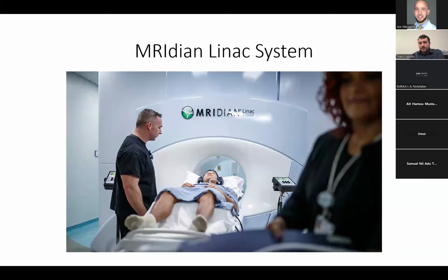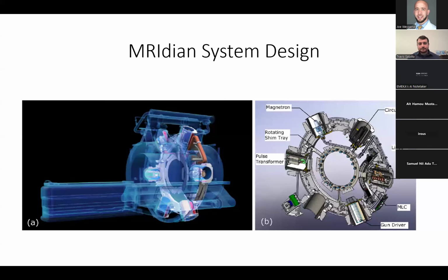So this is what it looks like now. As I mentioned, the more modern systems actually replace your tri-cobalt system with a linear accelerator. There are advantages to that. Mainly the treatment times are a little quicker, and you have a bit more flexibility when it comes to your dose distributions. But modern ones, as I mentioned, utilize a linear accelerator over the cobalt-based radiation.